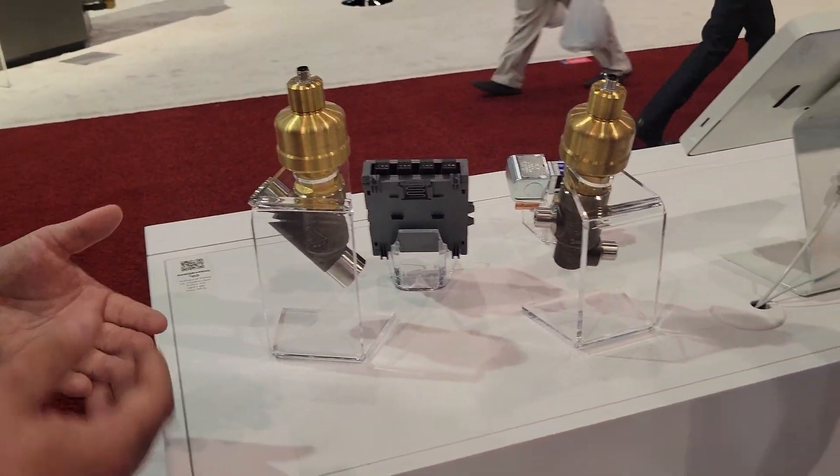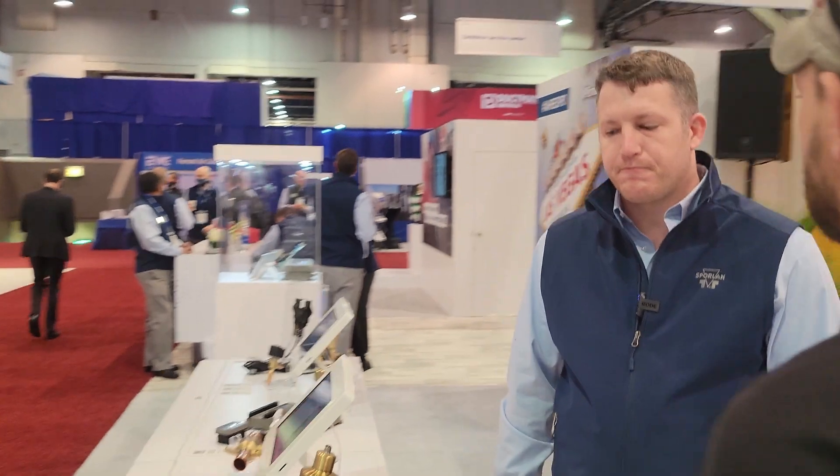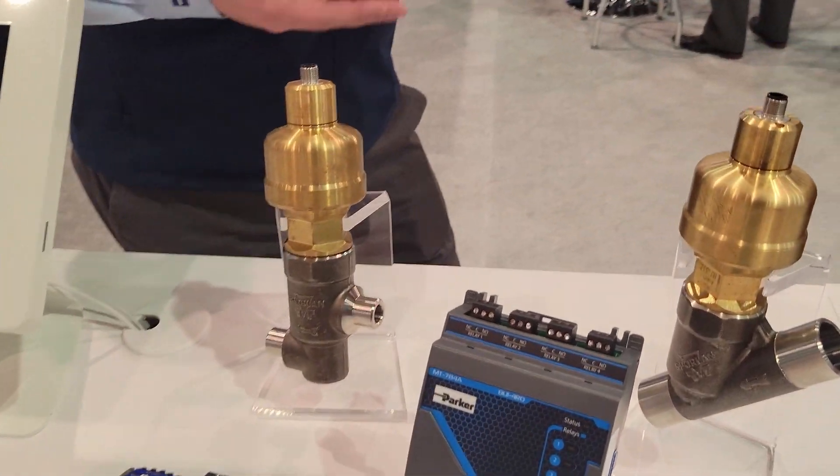Can you tell me a little bit about the valves, step rates, how you guys are controlling them — are you controlling them externally? So these products have a 2500-step step rate. We offer a valve positioner, and we would rely on the brain provided by the larger control system to do the algorithm for control of the valve.